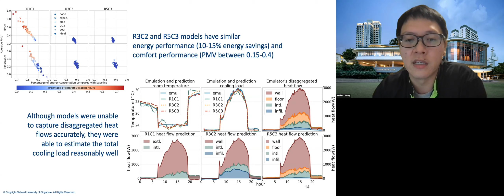In contrast, the R1C1 model shows a much larger variation in control performance and a very significant increase in comfort violation hours. The main reason is, if you look at the plot on the bottom, it's not very visible, but the R1C1 model tends to underestimate the cooling load in the afternoon. As a result, the space tends to be overheated.